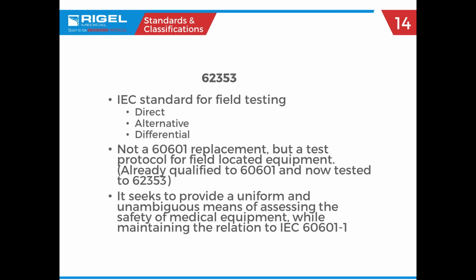The 62353 standard was never meant to replace the 60601 standards. It's just saying, like we said before, that if the device met the more strict standards during the manufacturing time, is it really necessary to test that intensely every single time you do a PM? So it just makes your life as a biomed simpler, while also staying in line with the more stringent 60601 standards.